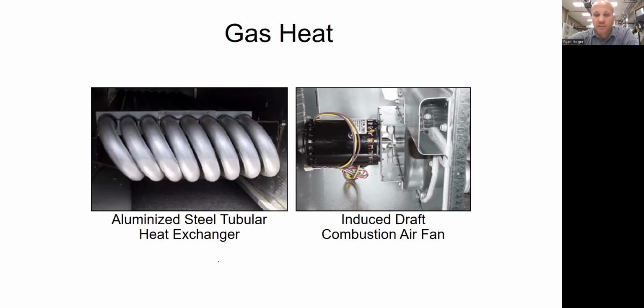And then there's an exhaust fan on there. We call that an inducer fan because it sucks air through the heat exchanger. This is where that little hood went, where it blows the exhaust out. And then the motor is physically inside the cabinet.